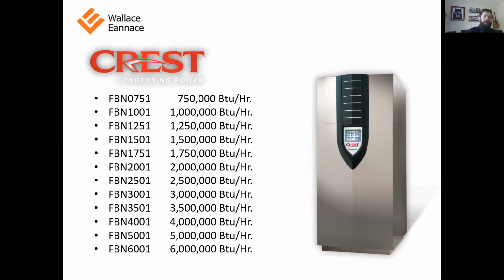the Crest. The Crest is our larger offering, going up to 6 million BTU. This is really the crown jewel of the Lochinvar product line, and frankly, the best condensing boiler on the market. And we can cover a wide range from 750,000 up to 6 million BTU, peaking at 25-to-1 turndown, 97, 98% efficient on a lot of these if your system's set up properly. And I'm going to go over that right now.